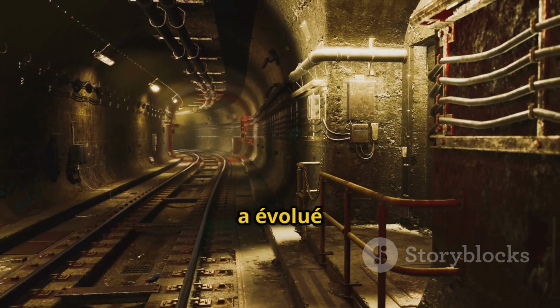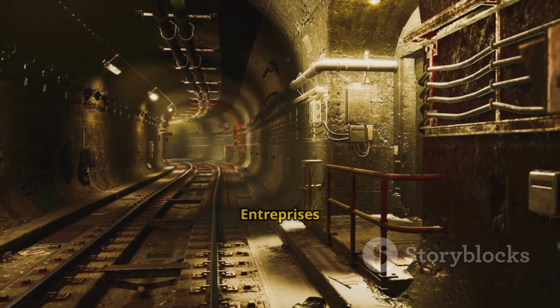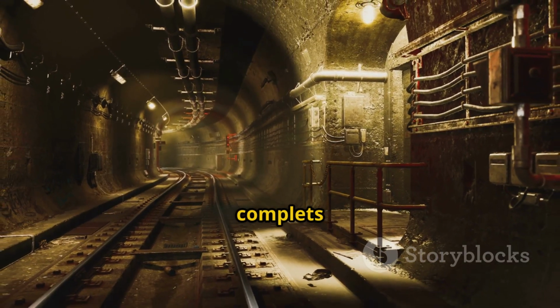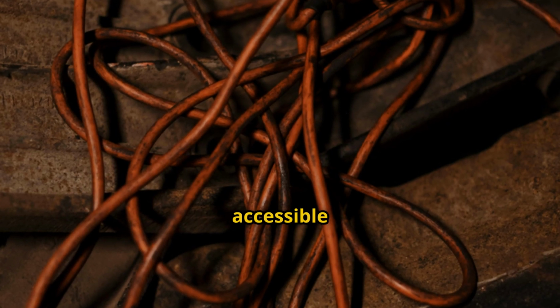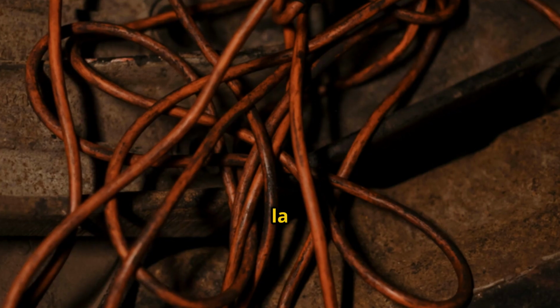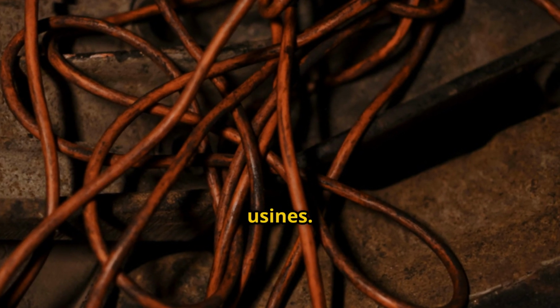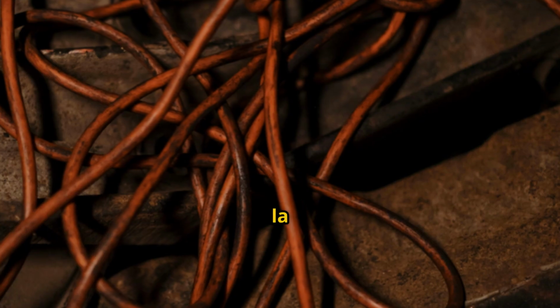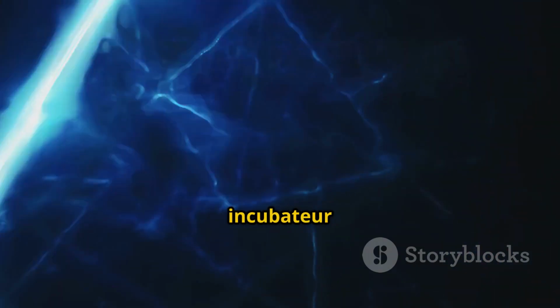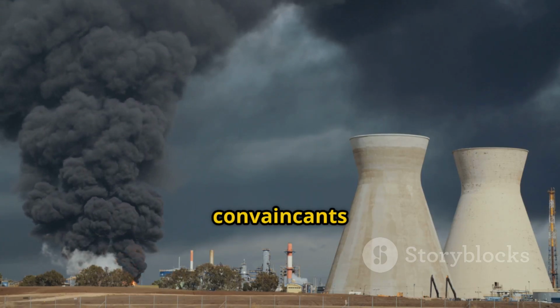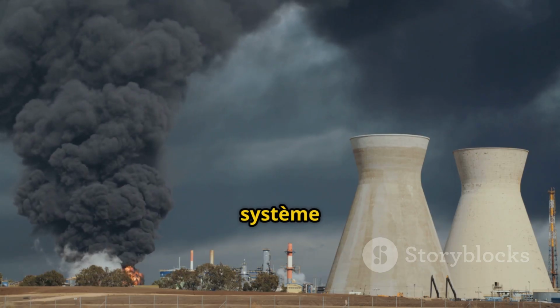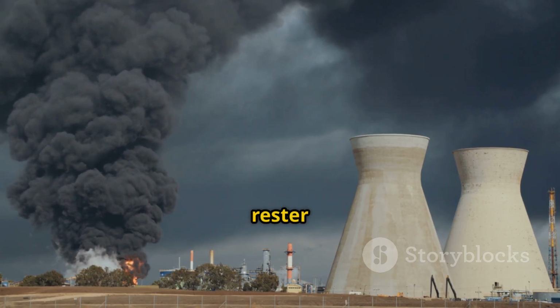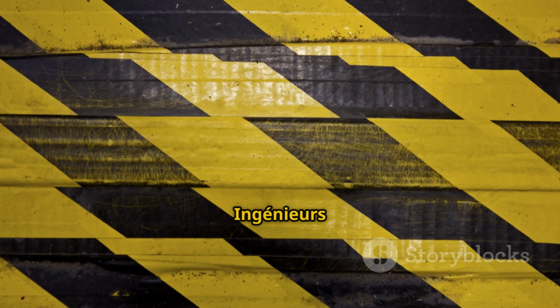When many of these cables are packed tightly together inside a sealed metal pipe, that heat has no way to dissipate. The ambient temperature inside the conduit could rise to dangerous levels, causing the cable insulation to degrade, become brittle, and eventually fail. This created a persistent risk of short circuits, equipment failure, and, most alarmingly, electrical fires. In an environment filled with flammable materials, a single electrical fault could have catastrophic consequences, making the conduit method a hidden but significant safety liability.